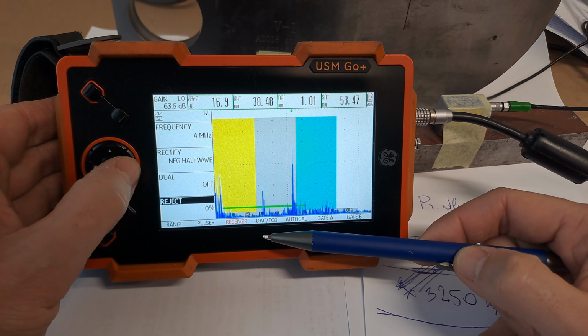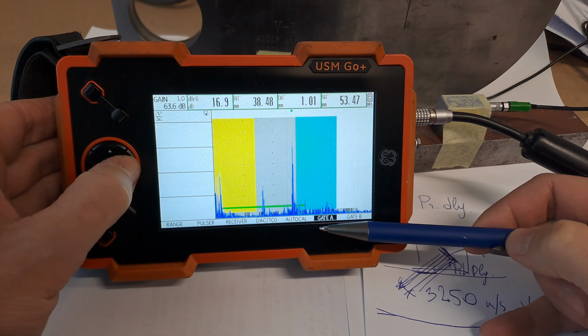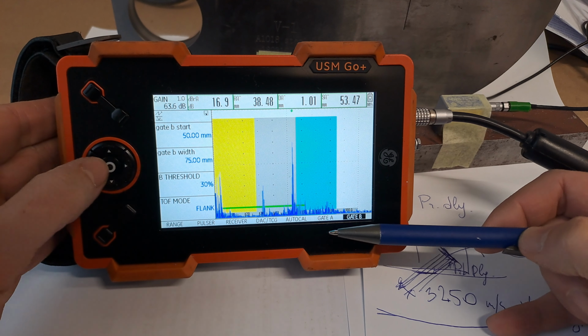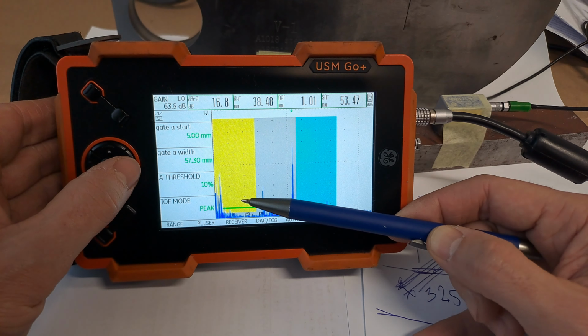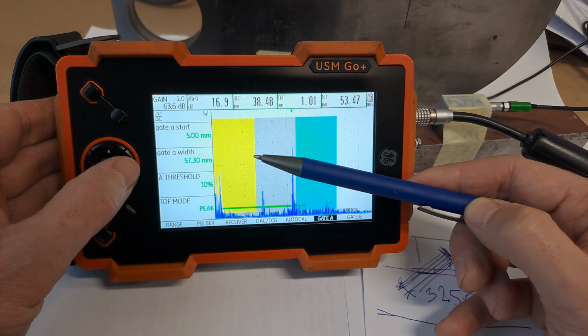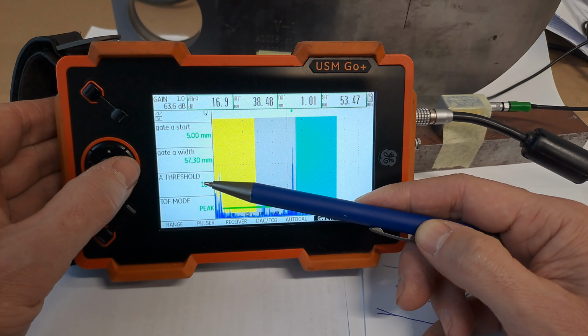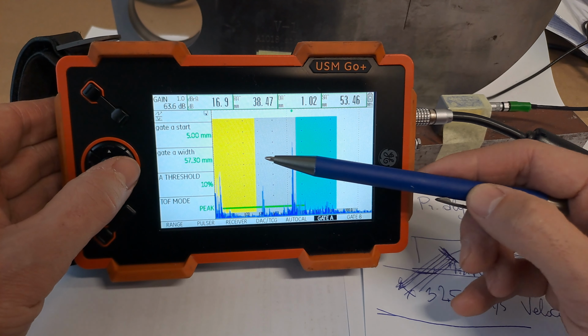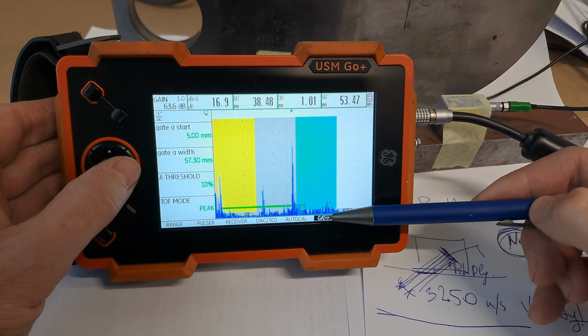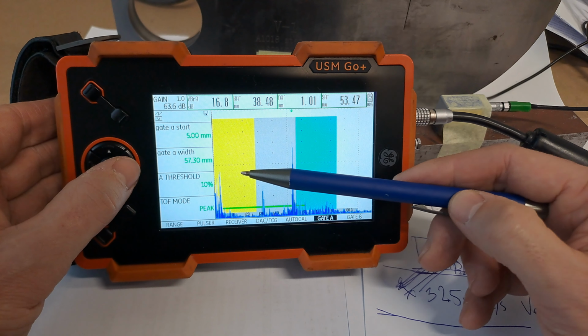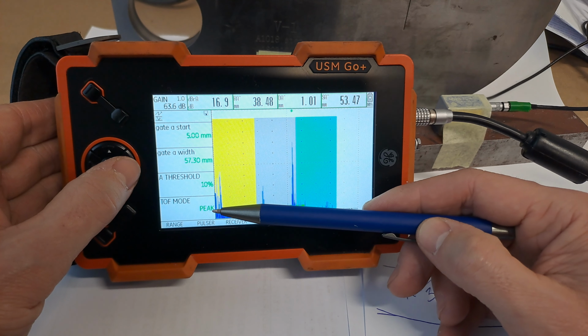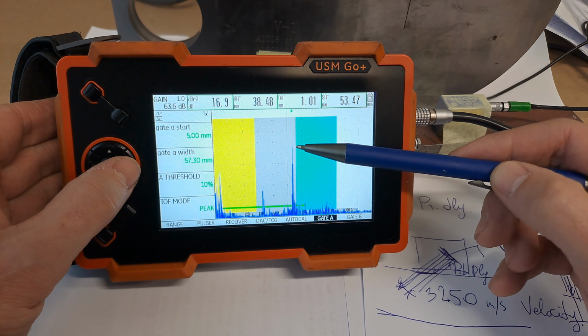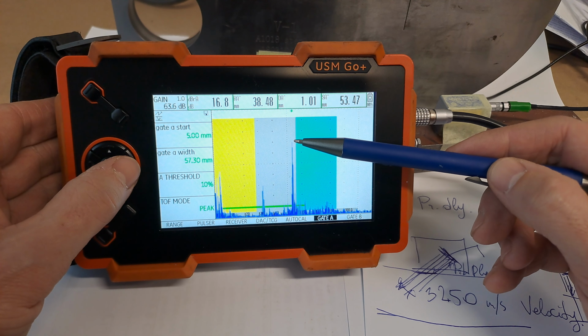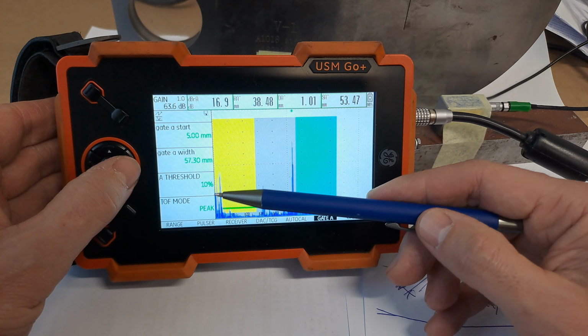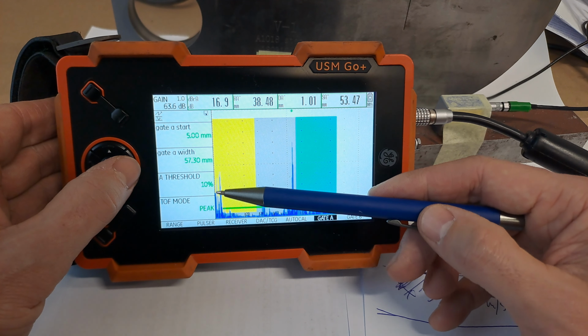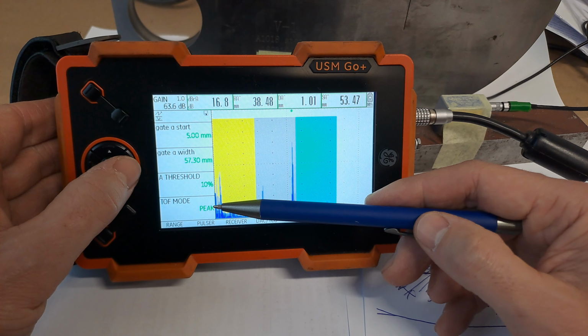Now, according to the book, the next setting is not DAC, is not auto, it's gate A. Gate A and gate B, this is this line. So we have the start of the line, the width of the line, and the threshold, the height of the line. I'll show how we use it, but here is the place we move the gate. And the TOF mode is peak, so when we measure this spike, it checks the peak of the spike. There are other modes here, the peak of the first spike and things like that, but we just use the peak setting here.